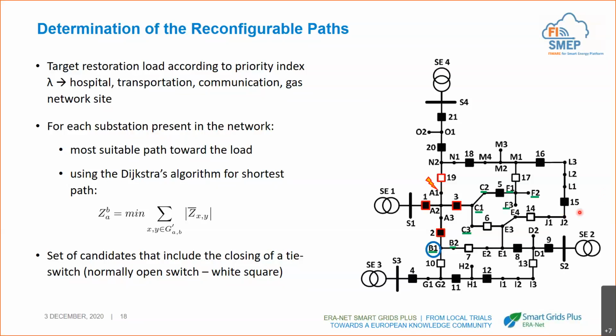For example, we can reconnect from the substation 3 by closing the switch 10, or we can close from the substation 2 by closing the switch 7. And these 2 paths are found because they are the shortest electrical path. In particular, they are the paths with the minimum impedance, so with the lower losses. But among these 2 paths, which is the best one, we have to determine with the service restoration algorithm.